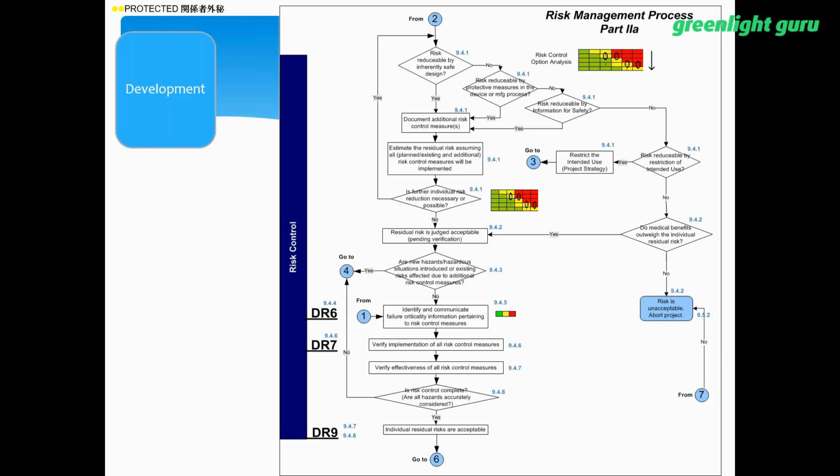Everybody knows about reporting through MDRs, et cetera, and you know what happens, unfortunately, if someone gets killed as a result of the device. However, if that device, by definition, is being used outside of defined life, then you still have to investigate that, but you may not have to take overt action because the device has been used outside life.